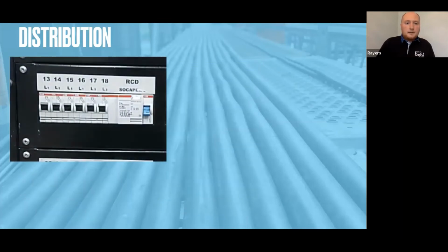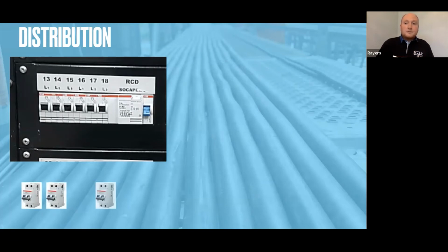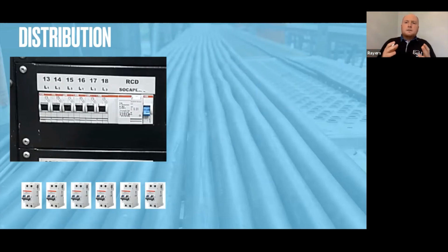As great as RCDs are in systems, they do present some problems. I invariably get questions from clients saying that when doing their power, an issue causes something to trip out and everything goes off. That's really important to look out for, especially if you're specifying power or asking for quotes or advice. I've taken a screenshot of an old distribution unit which shows an RCD present, marked RCD on the screen, meaning it's protected, which is fantastic since it protects people if there's an electrical fault.